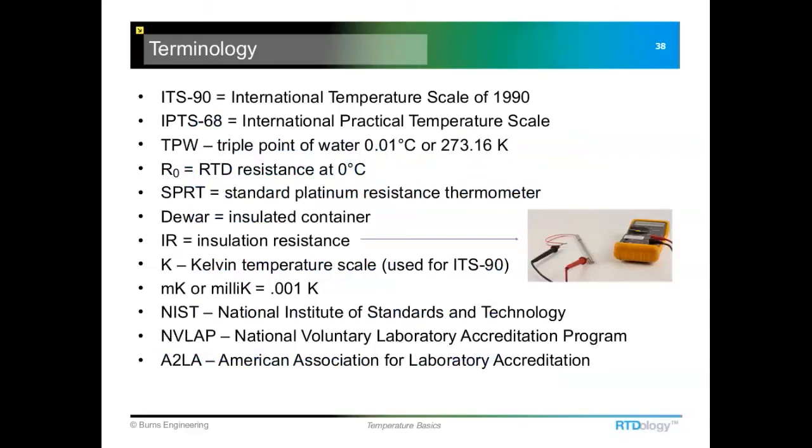And I guess I wanted to leave you today with some terminology. Some of the things that you will run into specifying RTDs. You may see ITS 90, which is the newest temperature scale, and then the IPTS 68. Also run into this fairly frequently too, in that there are what you will hear called CVD coefficients, or Callendar-Van Dusen coefficients. And those are what would be used when you're trying to match an RTD to a transmitter, for example, or some controllers and chart recorders and other peripheral devices.